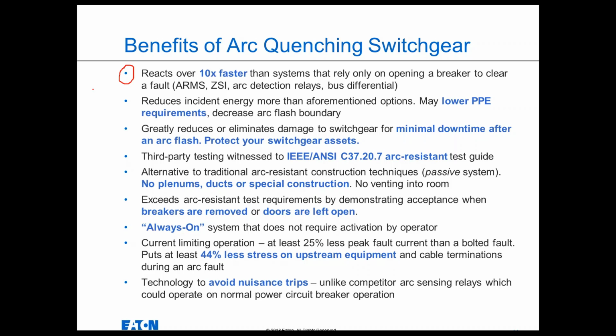And of course, it's that stress that can damage the secondary windings on your transformer, tear cables out of the termination, cause cable whip, and that sort of thing. So it's really important to avoid applying a bolted fault to your system whenever possible. And this system does not do that. It reduces peak fault current when it operates. And it's got technology to avoid nuisance trips. So it will not nuisance operate if you have a feeder breaker in the switchgear that clears a downstream fault.